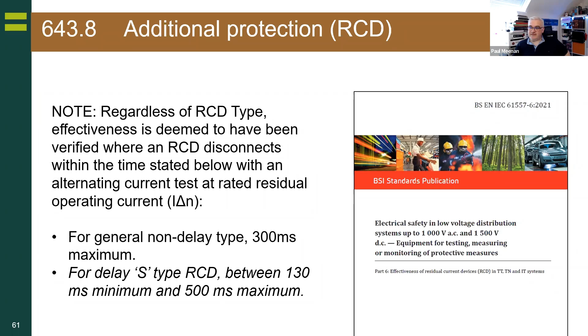Now, there's a lot of debate to be had about this. A lot of people could argue and have said, well, BS EN 61008 is a manufacturer's standard, and we've always kind of brought a manufacturer's test into the wiring regulations. There's more to it than that. There's far more to it. This table that used to give us all this wonderful guidance from one of the appendices that told us 300 milliseconds or 150 or 40, it's been deleted. It's gone. It's completely gone.